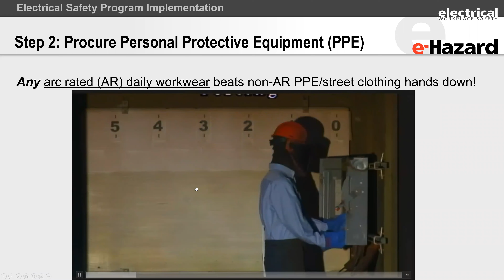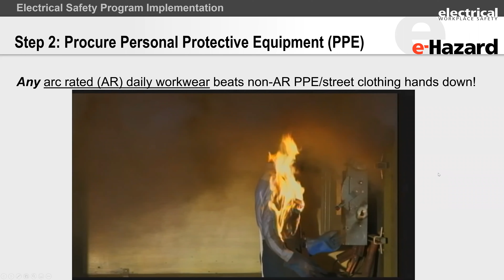Here, what you see is a mannequin exposed to an arc flash using normal street clothing, or even if it's not street clothing, even if it is industrial type clothing but it's not arc rated, what you see is clothing ignition. And once you have clothing ignition, it can get bad or it can get very bad. Hugh's going to talk about a fantastic test that he did with 3 mannequins side by side, where he'll talk about ignition versus melting and dripping, because you can get bad and then you can get very bad.